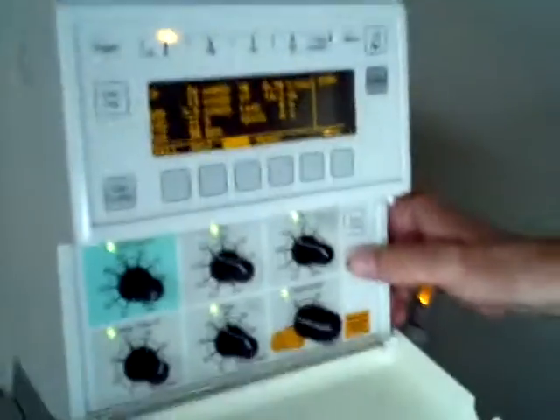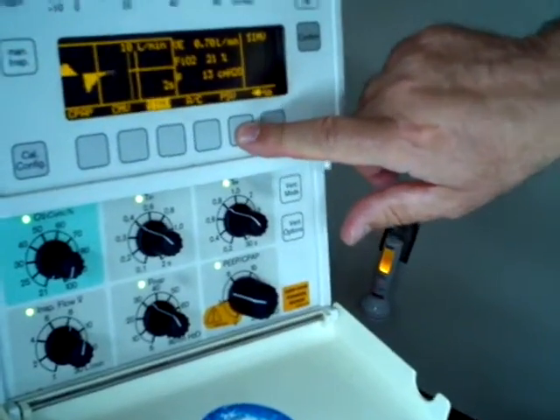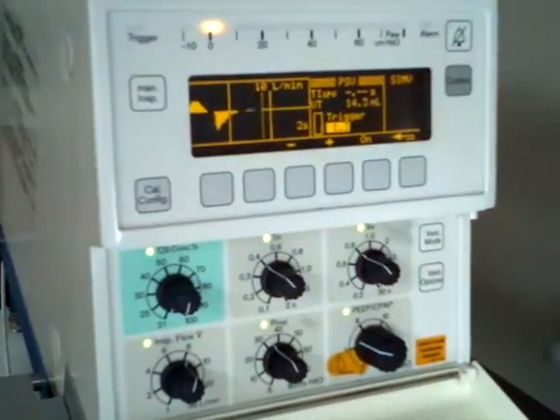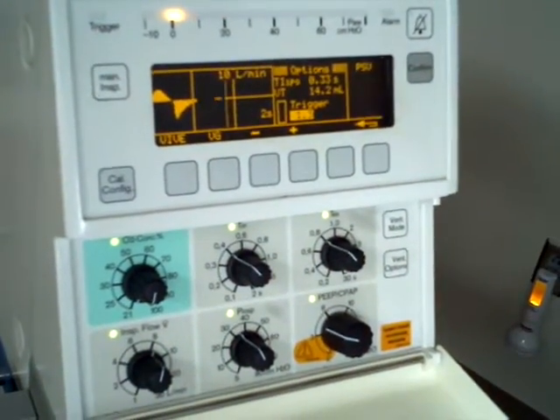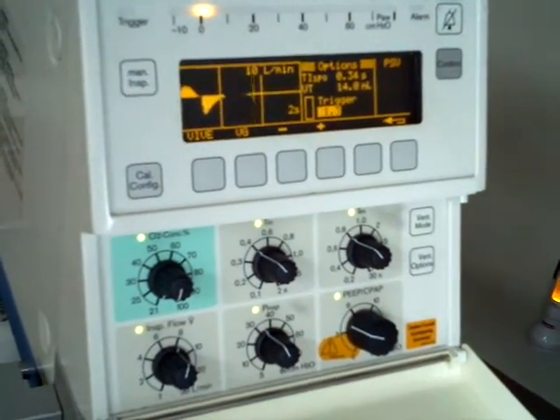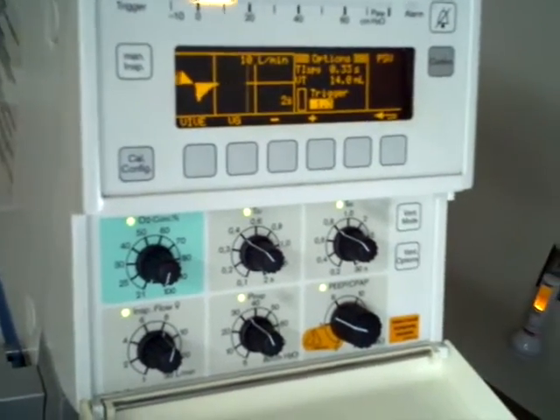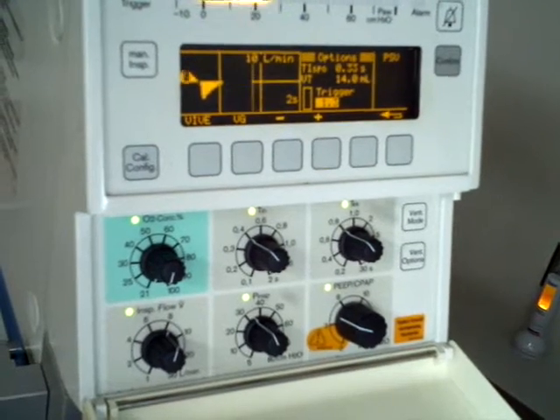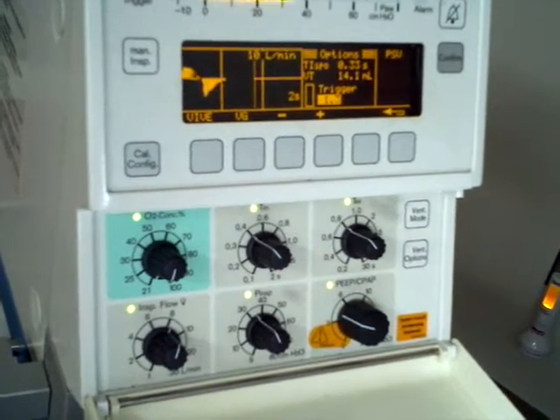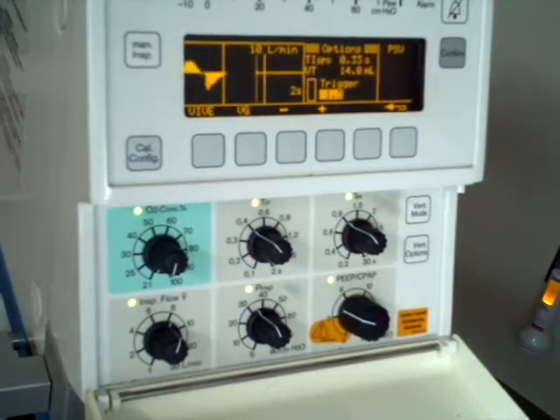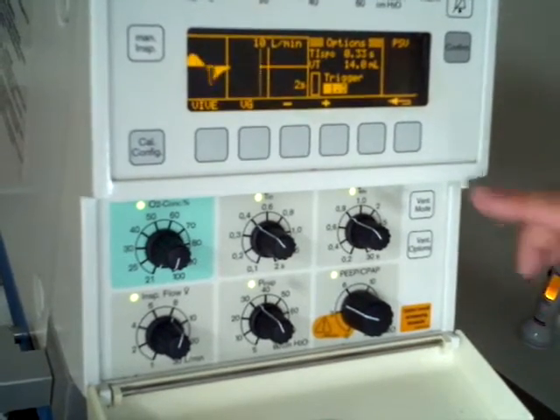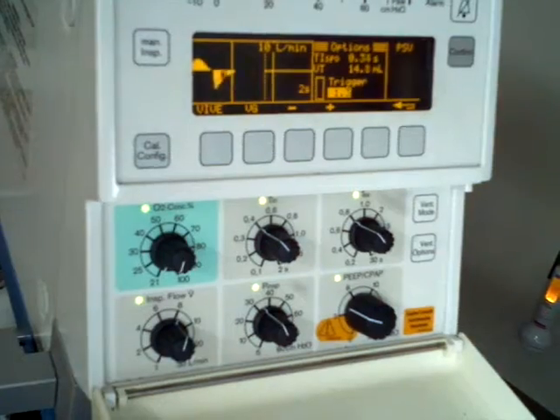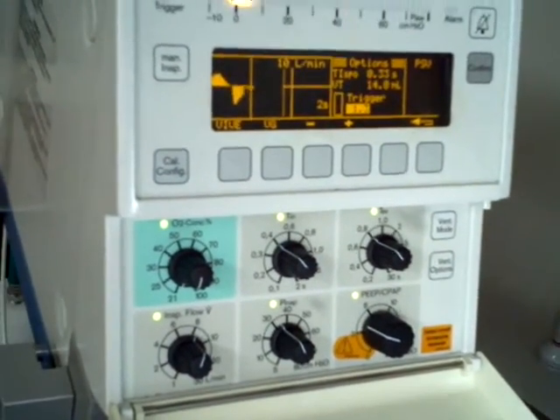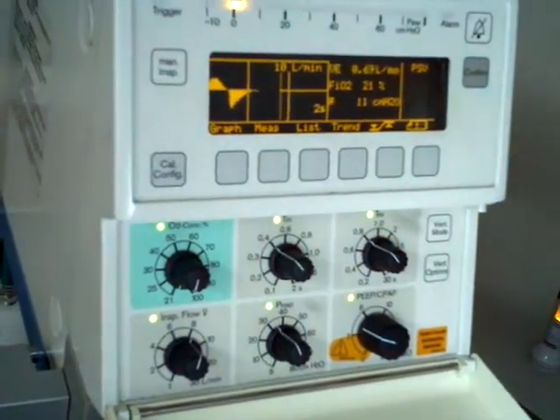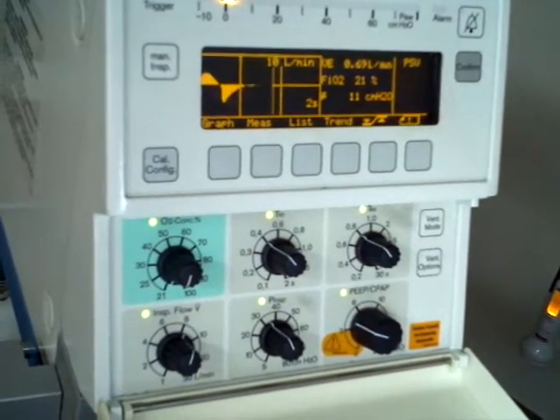Pressure support mode. Again, mode change. Vent mode. PSV is pressure support ventilation. It's a little bit different on this ventilator. Okay, now we're in PSV. The big difference with pressure support on this is it allows the baby to do their own inspiratory time. So we're still setting a rate, which in my mind doesn't make it pressure support anymore. We'll leave the rate the same. Set the pressure support level, which is your PIP. Let's say we want a tidal volume of 11.